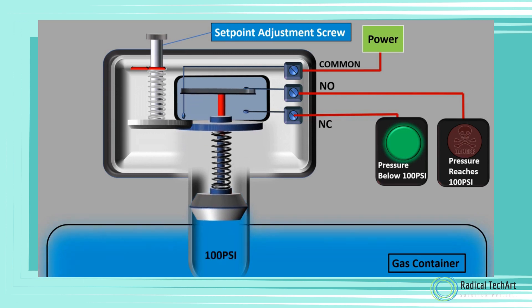So when the inlet pressure reaches 100 PSI, the piston is forced upwards by the inlet pressure, compressing the range spring, and the piston will hit the trip button on the micro switch and change it over. Now the normally open contact will get power and the red light glows while the green light switches off.